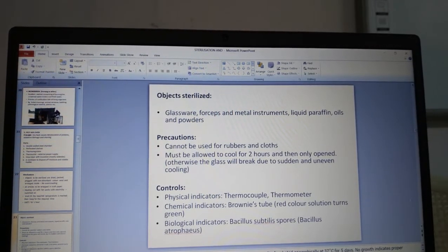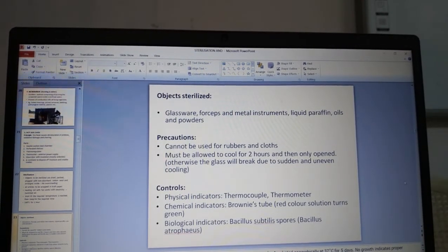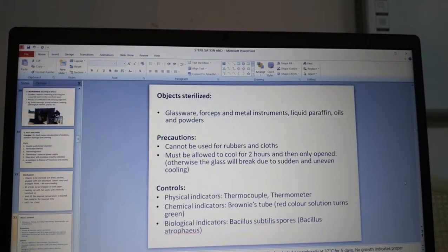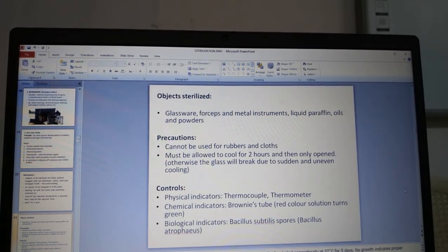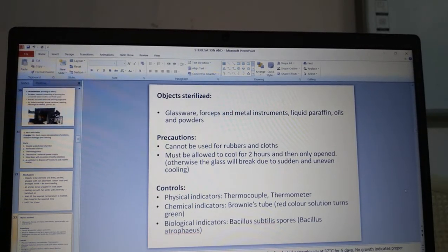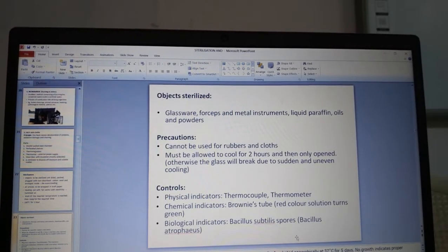To check the efficacy of the hot air oven, three kinds of controls are used. Physical indicators are thermocouple and thermometer. Chemical indicators are Brownie's tube — a red color solution that turns green once sterilization is complete; if it doesn't turn green, the efficacy is not good. Biological indicators use Bacillus subtilis spores (Bacillus atrophaeus) — after sterilization, strips containing the spores are inoculated into tryptone soy broth or Robertson cooked meat medium and incubated anaerobically at 37°C for five days. No growth indicates proper sterilization.